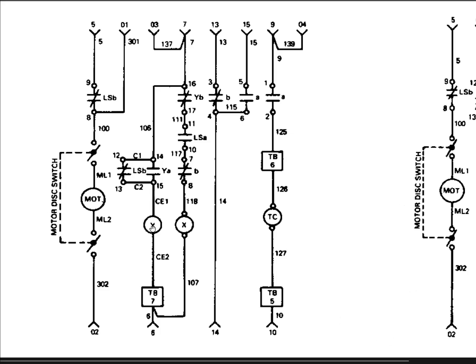Now, just as a note for everyone, the motor is going to be an 88 or it's going to be MOT or M. Then you're going to have TC or 52T or something along those lines for your trip coil. And then for your closed circuit, it's going to be a 52X or a CC. And this Y is your anti-pump relay for your closed circuit, so that you don't sit there and pump over and over again.